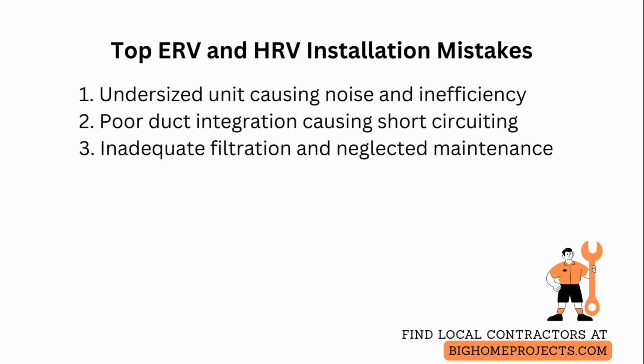A third concern is using inadequate filtration or forgetting maintenance, which reduces performance and fouls the heat exchange core, so specify appropriate MERV filters, install easy access filter frames, and set a maintenance schedule visible to occupants.